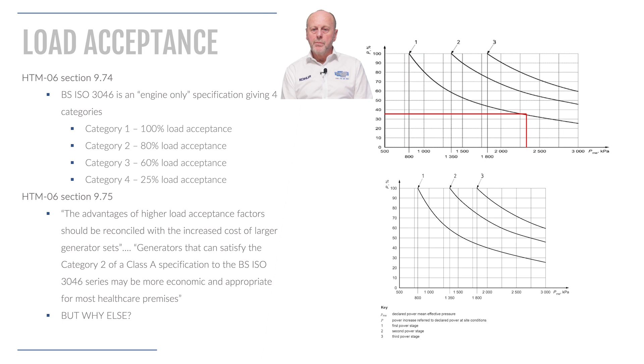In section 9.75 of HTM06, it states the advantages of higher load acceptance factors should be reconciled with the increased cost of larger generating sets. Generators that can satisfy the Category 2 of Class A specification of ISO 3046 series may be more economical and appropriate for most healthcare premises. So why? Let's take a quick look at some more comparisons to better understand some of the mismatches and their potential impact.